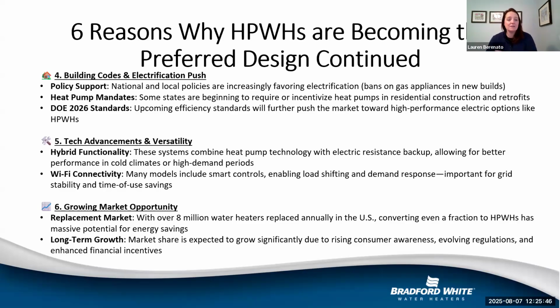So for technical advancements and versatility, we have hybrid functionality. These systems combine heat pump technology with electric resistance backup, allowing for better performance in cold climates or higher demands. Wi-Fi connectability is something that we've seen a lot of customers asking for. Many models do include smart controls enabling load shifting and demand response. It's important for grid stability and time of use savings. Another thing too, I think, is if it's a second home and you want to know what's going on with your water heater, that's one of the things where Wi-Fi connectability is key.